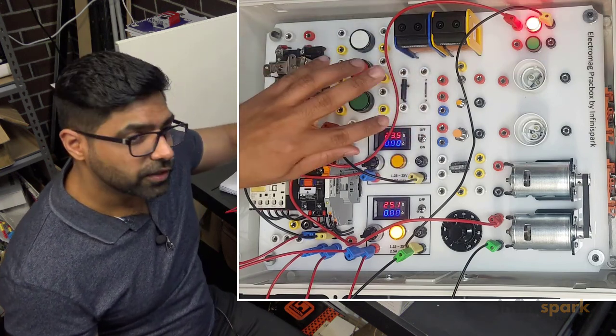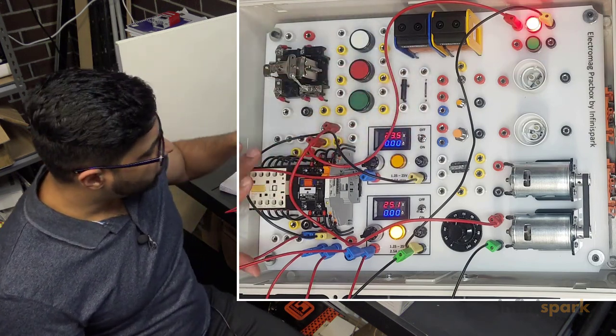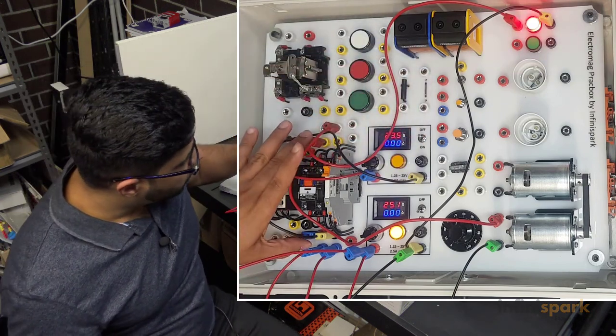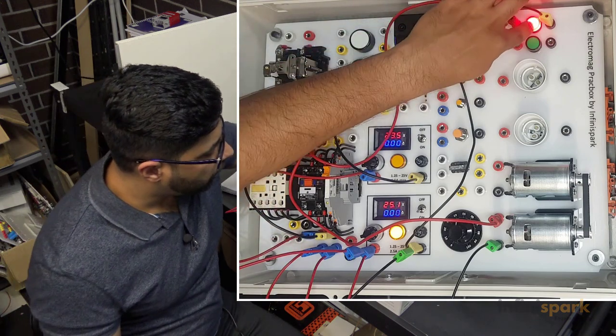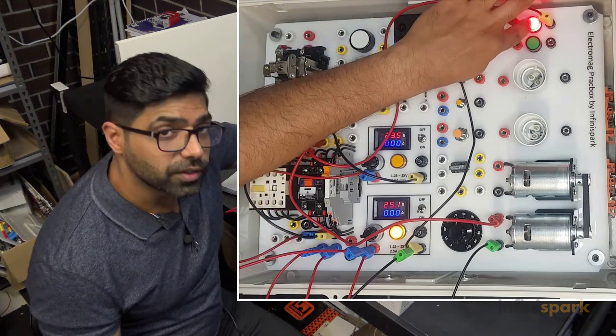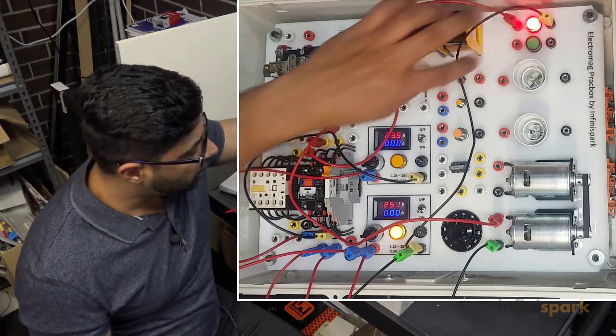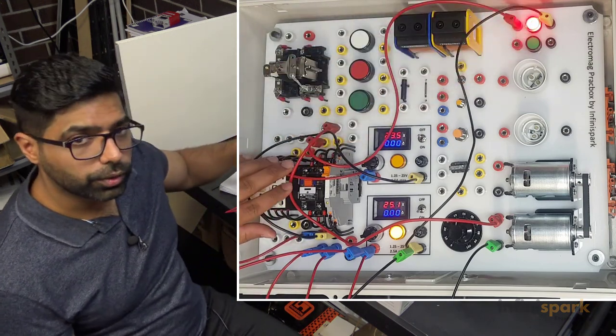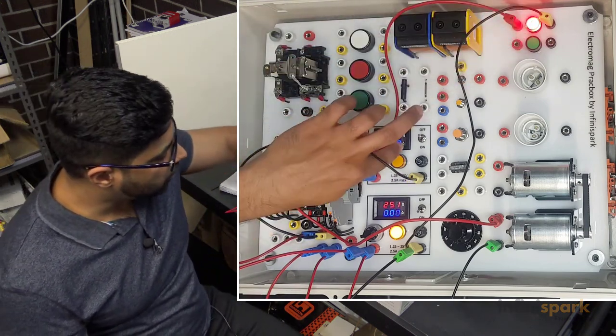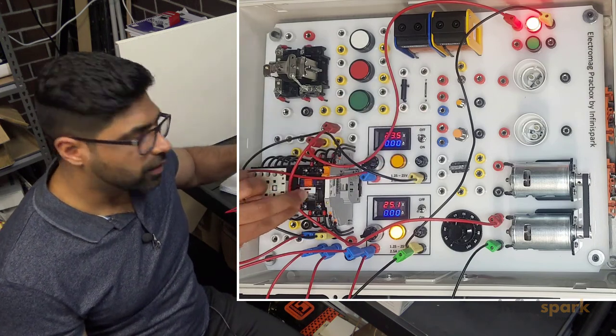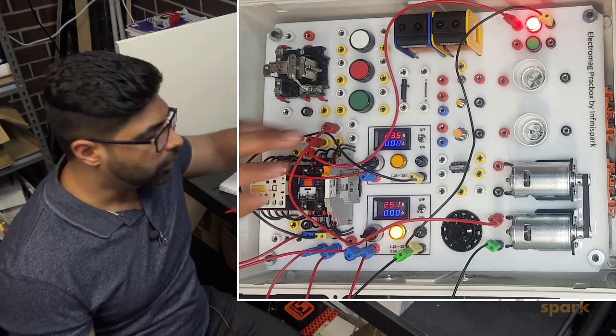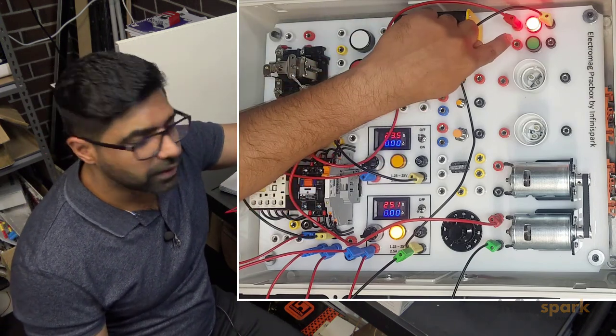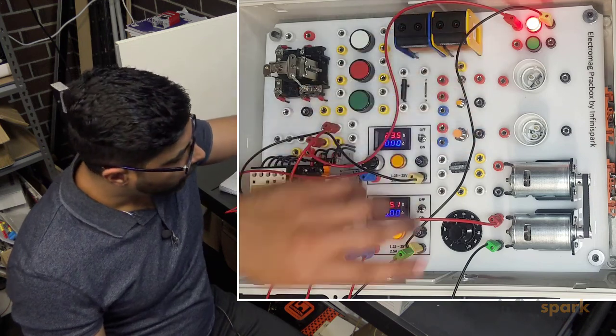The reason this is happening is because the contact powering this lamp is connected to normally closed. When I turn this on, the relay energizes, the normally closed becomes open, which disconnects the lamp.